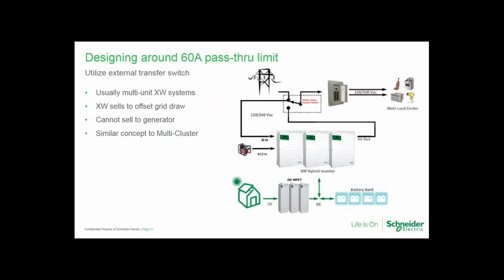And then, of course, designing around the 60 amp limit we discussed, with multi-unit systems. Here we can see the use of what we call a whole house transfer switch. This allows you to get around the 60 amp limitation because you're only connected to the input when the grid is present, and you're exporting your solar energy to mitigate the demand from the grid. If the grid goes down, all the load is transferred to the output side of the inverter. This is the preferable means of installing multi-unit systems that exceed 60 amps continuous, and we want to protect those internal relays.